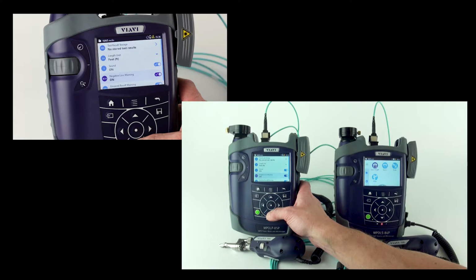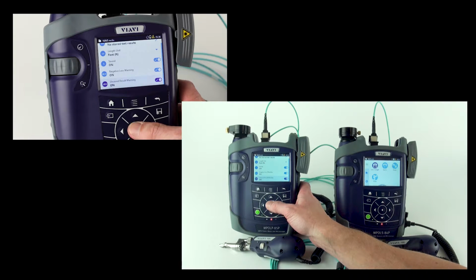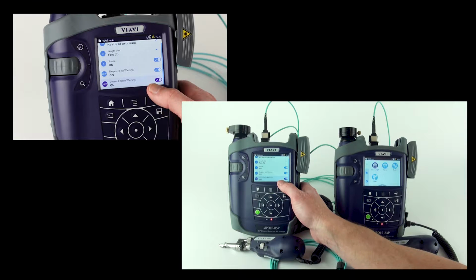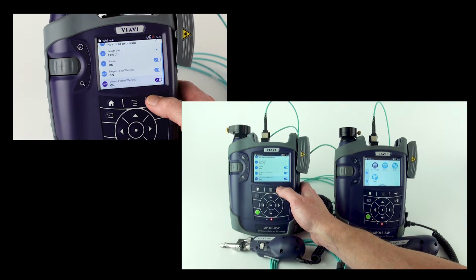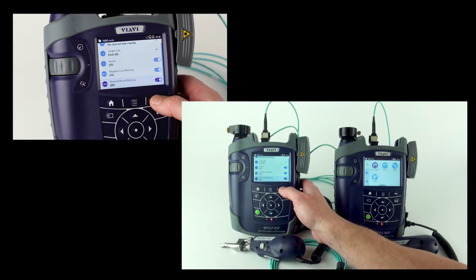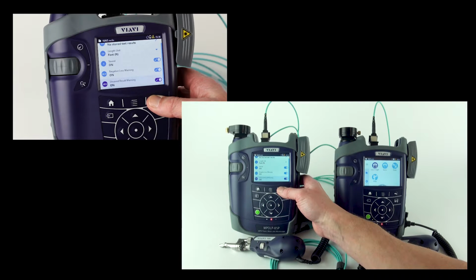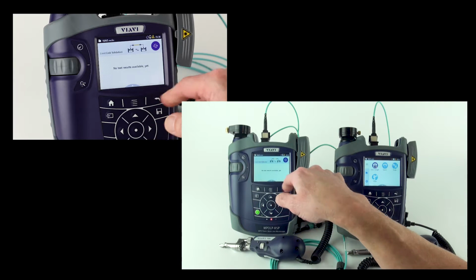You can also have a negative loss warning on or off. By default it's on, and we recommend you leave it that way. And you have an unsaved result warning. If you're needing to save results, you want to leave this on, and it prevents you from exiting the results screen without having saved results. If you're just testing and you don't care about saving, you're going to want to turn that off so you're not being annoyed by prompts to save results.